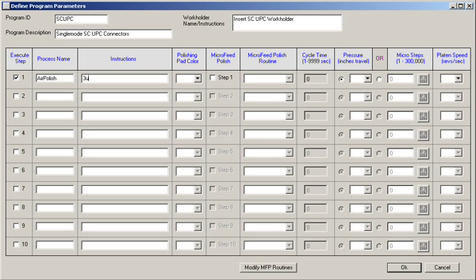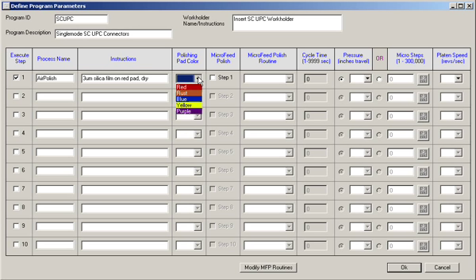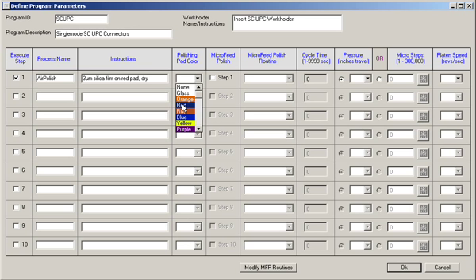Prior to commencing this and subsequent steps, the technician will be presented with instructions associated with the upcoming step. This typically consists of polishing film type, rubber pad type, solution if any, to be used with this particular step. As a visual reinforcement for the technician, the pad color can be selected from a pull-down menu.